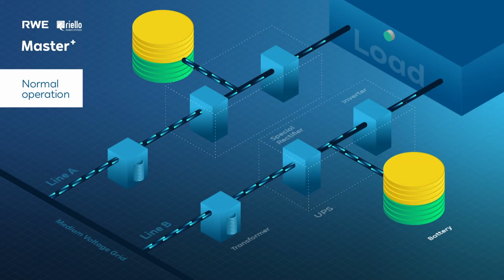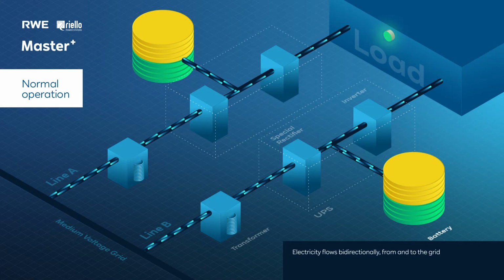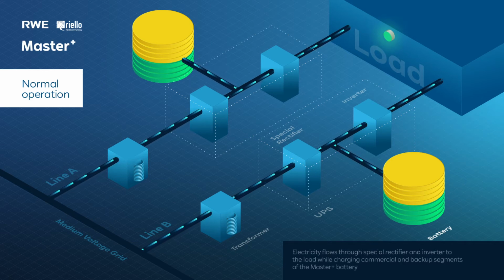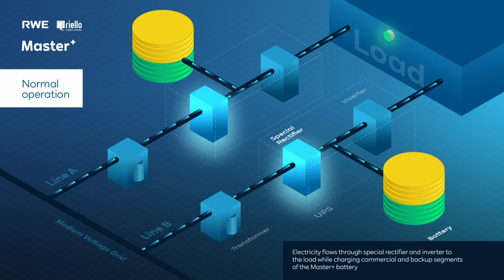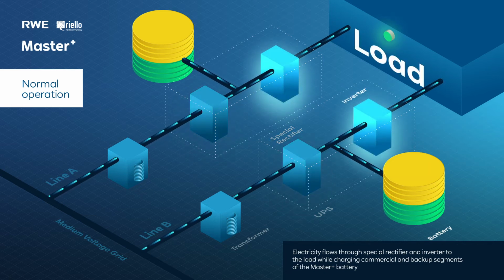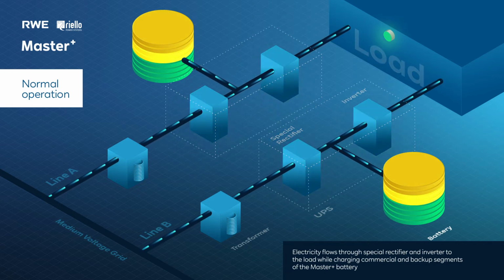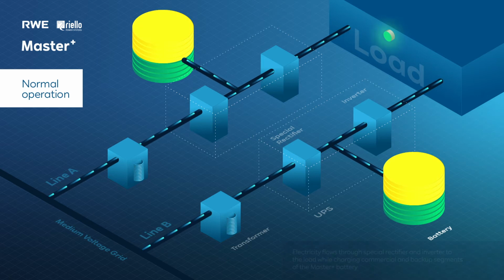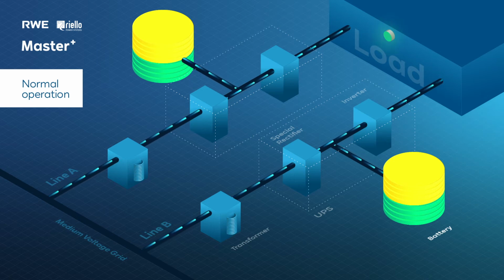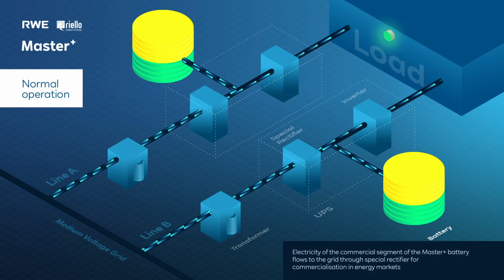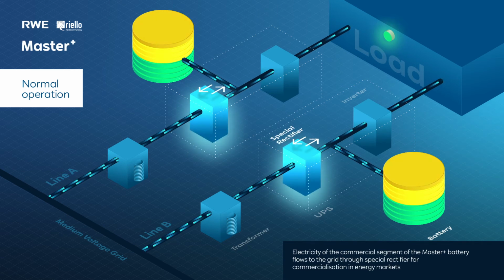When the Master Plus is in normal operation, the electrical current can flow bidirectionally from and to the grid. The electrical current flows through the special rectifier and the inverter to the load while charging a commercial segment of the Master Plus battery, used only for commercialization purposes, and also keeping the backup segment at full capacity. Furthermore, electricity stored in the batteries can flow to the grid through the special rectifier also for commercialization purposes.